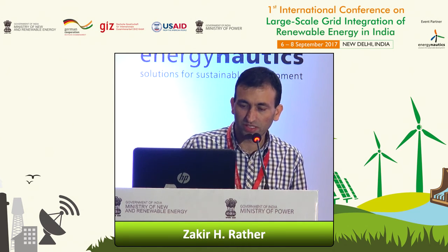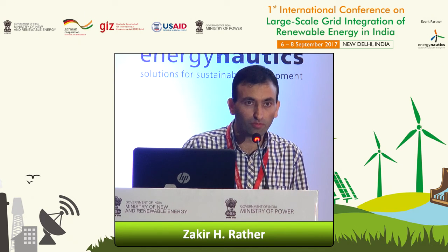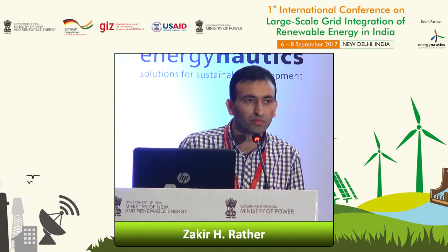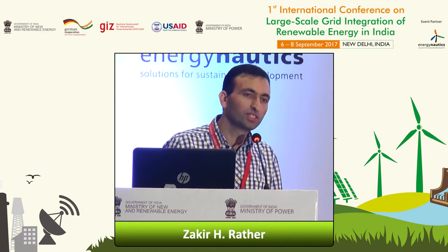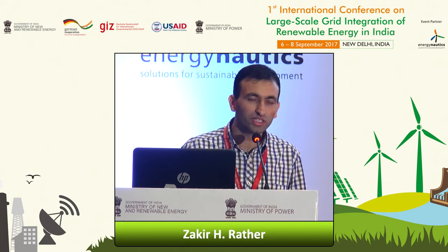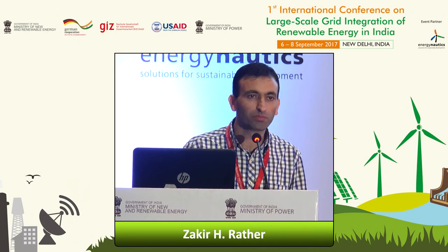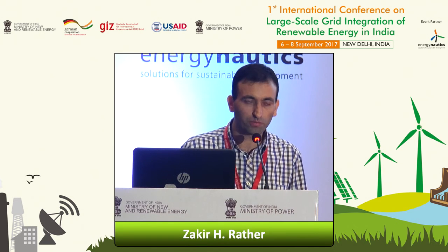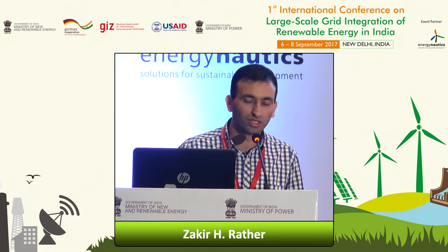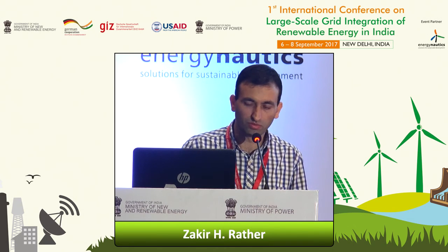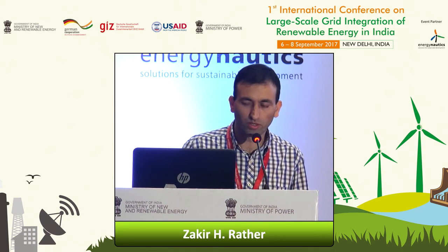Yeah, so this is one of the studies, on the left side, trying to validate a detailed wind farm model against an equivalent wind farm model. For example, at the wind farm level, if you look at the dynamic analysis of a wind farm, for a voltage event, each wind turbine is going to see different voltages compared to the other wind turbines within the wind farm. So when we try to model an equivalent power plant of this wind farm, we need to capture those issues in the equivalent model. Similarly, the wake effect, which we will talk about a bit in the next slide, is also one of the important points we should take into consideration while building a model of a wind power plant.